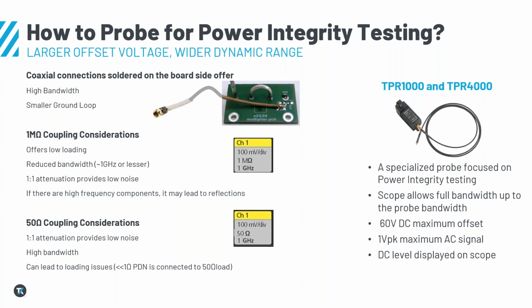Another way is to load it with 1 mega ohm coupling. Our differential probes are like high voltage probes. Passive probes come with a default 1 mega ohm termination. That's good if you're looking for lower loading. If you don't want to load your setup, then this is the best way. But the problem with this one is that you cannot have a higher bandwidth; generally the bandwidth will be less than a gigahertz. If it's 1:1, then it will have the lowest noise. But if it is a higher attenuation, like 10:1 or 100:1, then the noise in the system will be amplified by that factor, so you should be mindful of that. There can also be some high frequency components, which can be reflections, and you should be careful, as they can come onto your measurement and may give you wrong results when you are using 1 mega ohm termination.